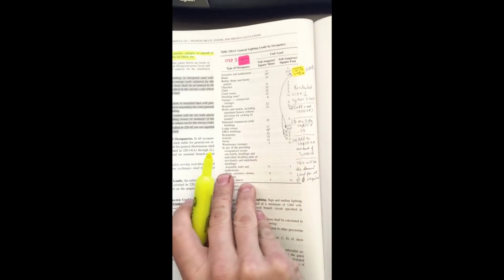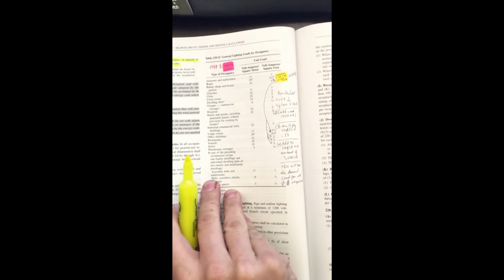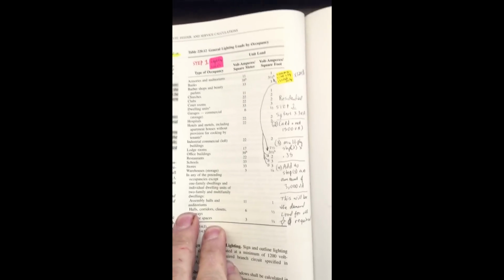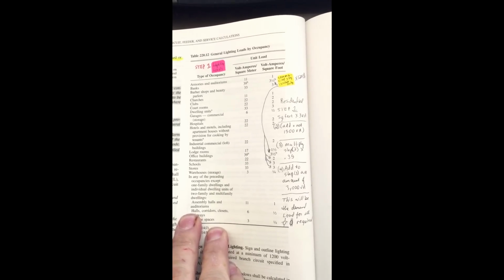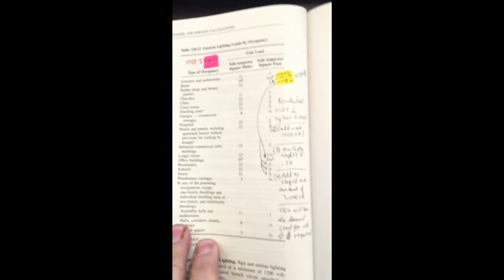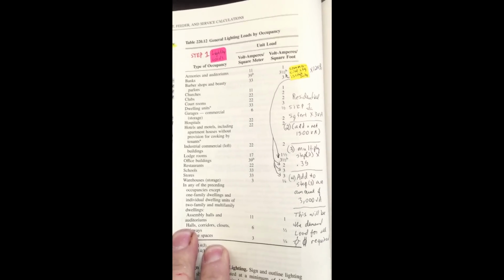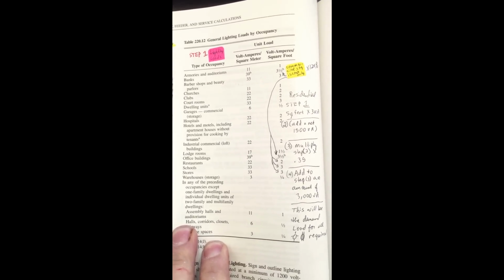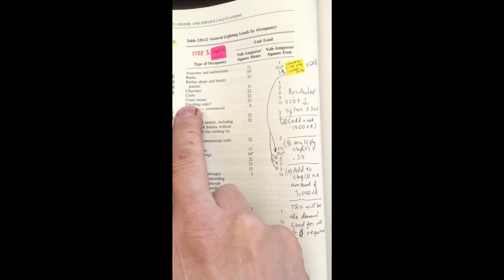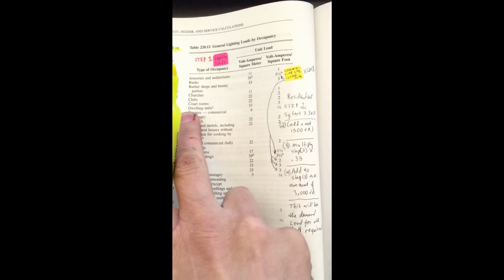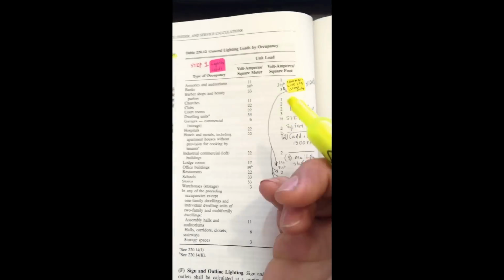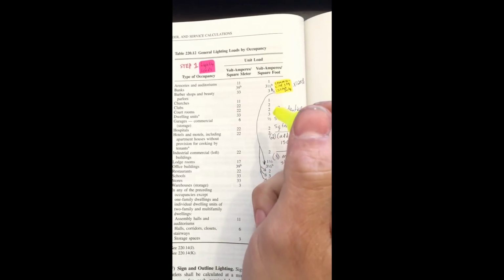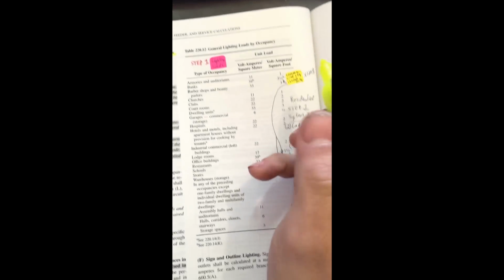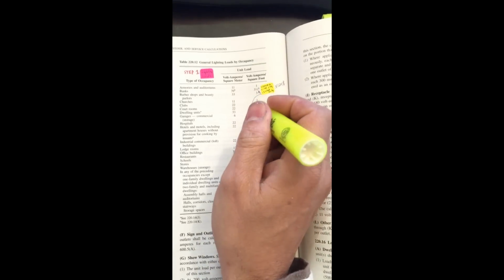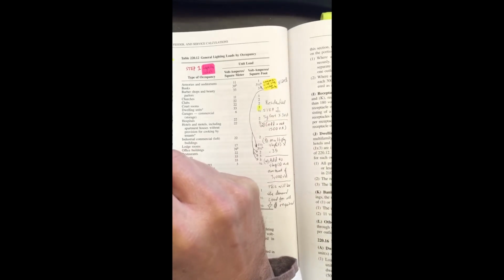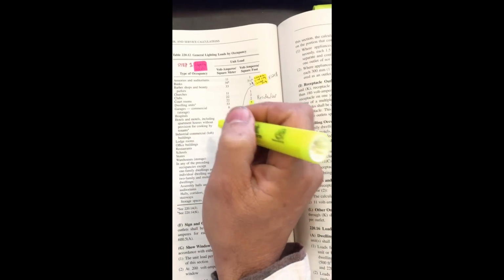And so if you look on page 68, under 220.12, you'll see a small table here on the right-hand column at the top of the page. And you'll notice I've got a few notes written in here, and let's go through these notes real quickly. First and foremost, you'll notice that dwelling units is listed about 6 or 7 down right there under dwelling units. Got the little tiny letter A next to it, and it says over here in this last column, number 3. So this works out to be 3 volt amps per square foot for a dwelling unit.